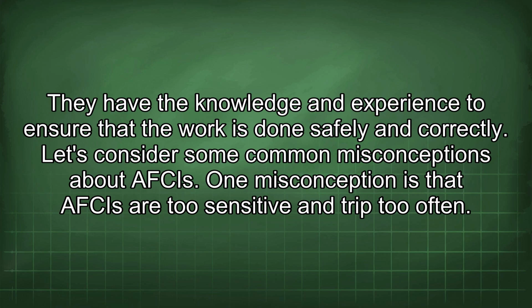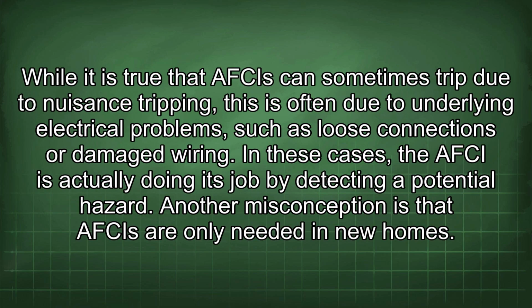Let's consider some common misconceptions about AFCIs. One misconception is that AFCIs are too sensitive and trip too often. While it is true that AFCIs can sometimes trip due to nuisance tripping, this is often due to underlying electrical problems such as loose connections or damaged wiring. In these cases, the AFCI is actually doing its job by detecting a potential hazard.